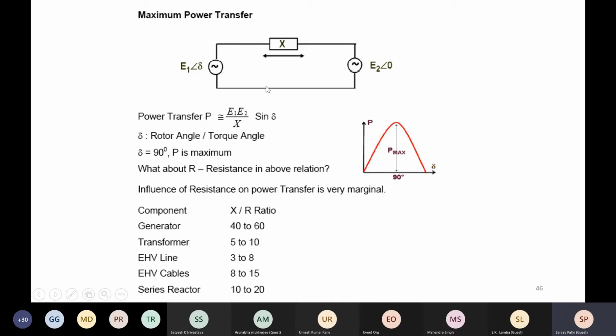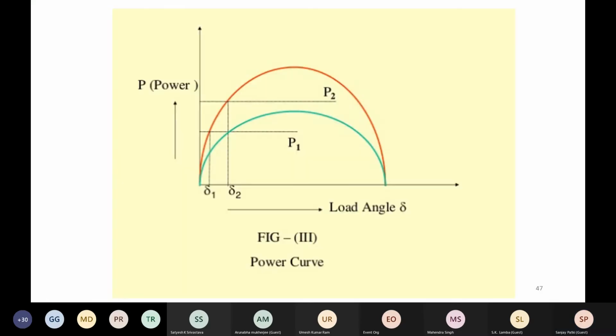Usually the load point of the generator would be around 60-70 degrees, and that is the optimal point which will keep enough stability margin so that the machine doesn't lose synchronism when there is a fault. The basic parameter for this is the X by R ratio. So basically this reactance and the X by R ratio influence this load angle.